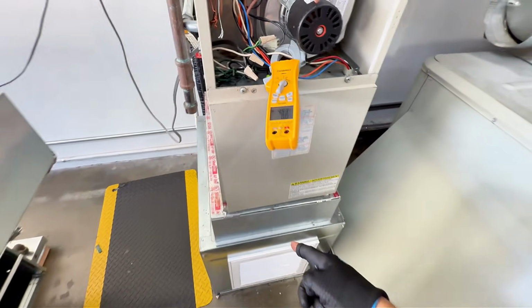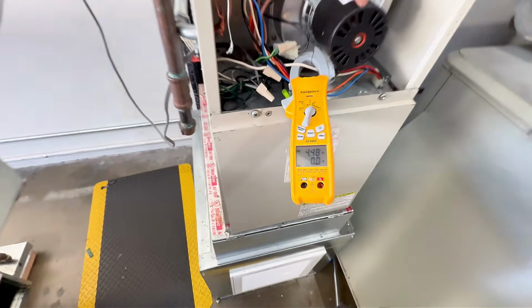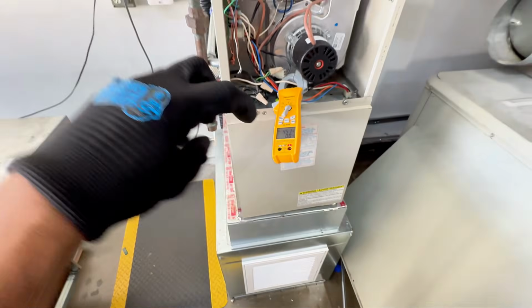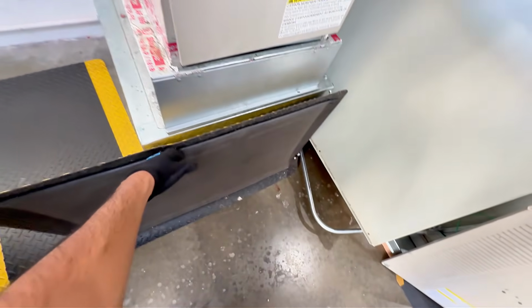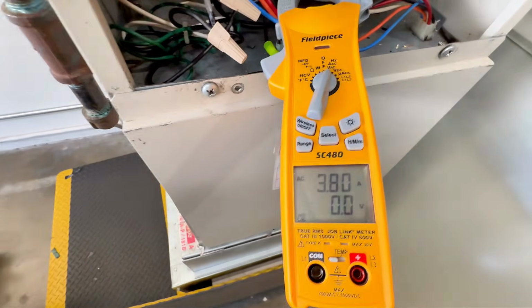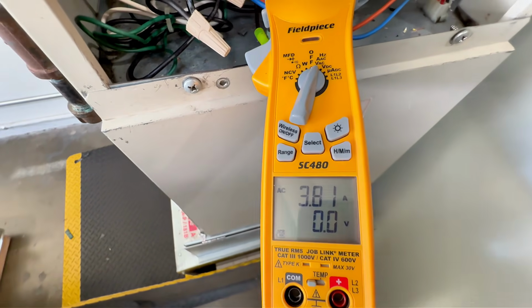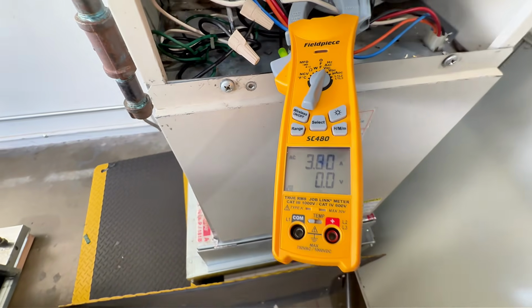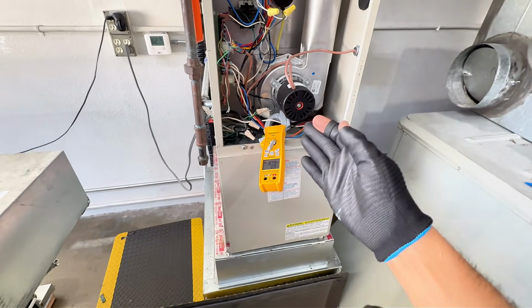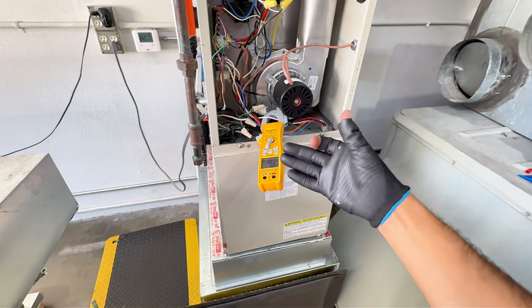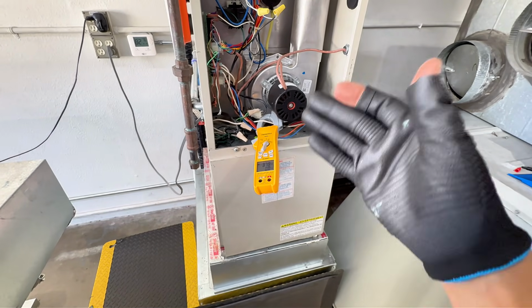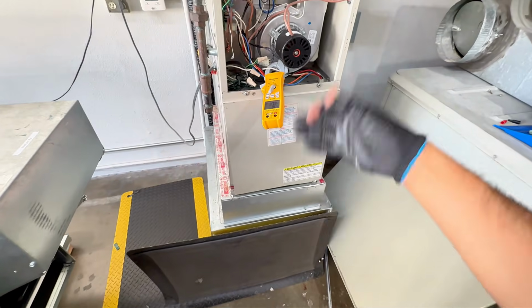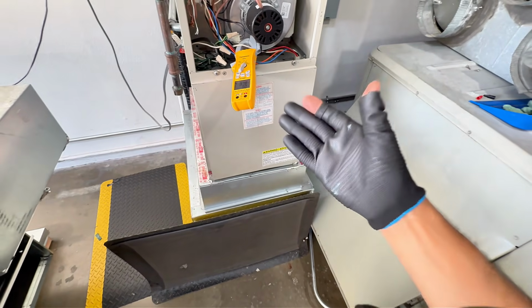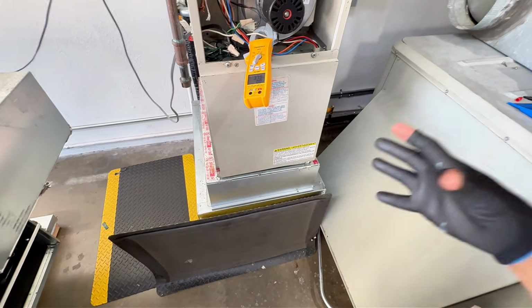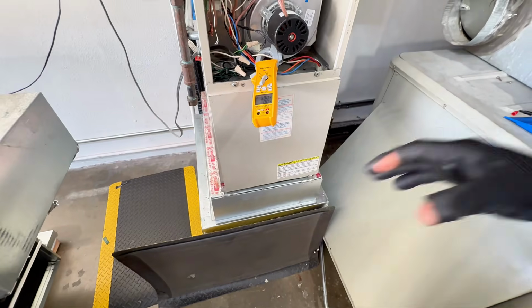So what's going to happen when I close the return? That amp draw there, 4.5, is it going to go up or is it going to go down? So it was at 4.5. Let's go ahead and create a restriction. Okay, what happened to it? It went down. You see now we're at 3.8, about 0.7 less. So this motor here, permanent split capacitor motor, this is the one with the capacitor, right? With this specific motor, it doesn't know that there's a restriction. It's just gonna work with what we're supplying it with. So now that we created a restriction, there's less airflow, less to work with, less current.